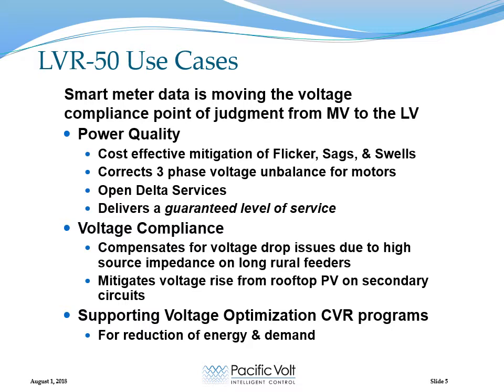So power quality applications include mitigation of flicker, sags, and swells. It can be used to balance three-phase voltages for unbalanced motors. It can be used to compensate for the open delta services where the phase angles tend to collapse and give you an unequal delta voltage. And in general, it delivers a level of service that otherwise is difficult for utilities to provide.